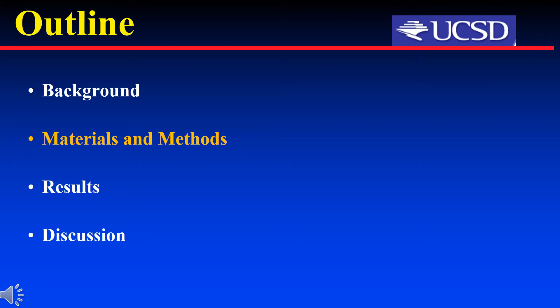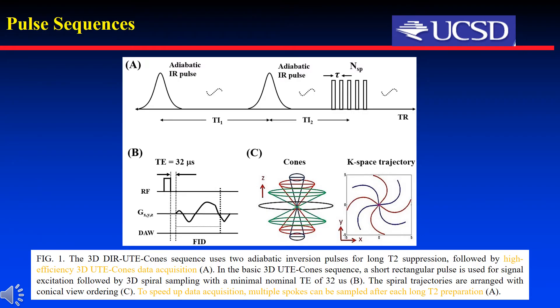The following are the materials and methods. The proposed 3D DIR-UTE-CONES sequence uses two adiabatic inversion pulses for long T2 suppression, followed by high-efficiency CONES data acquisition. In the basic sequence, a short rectangular pulse is used for signal excitation, followed by 3D spiral sampling with a nominal TE of 32 microseconds. The spiral trajectories are arranged with conical view ordering. To speed up data acquisition, multiple spokes can be sampled after each DIR preparation.